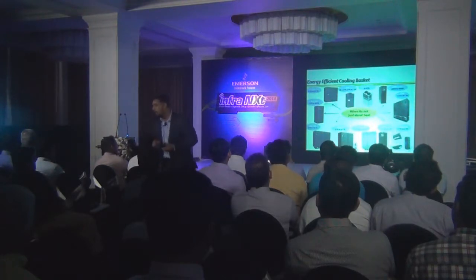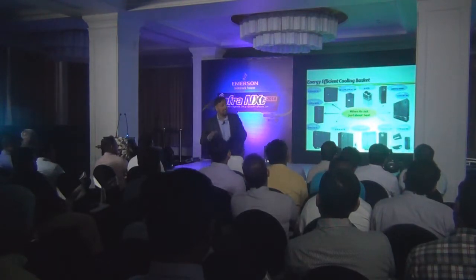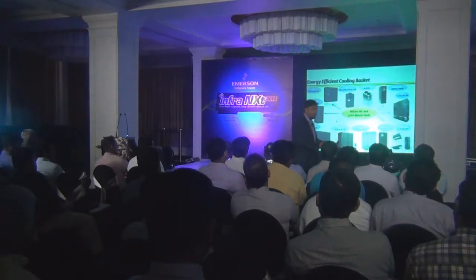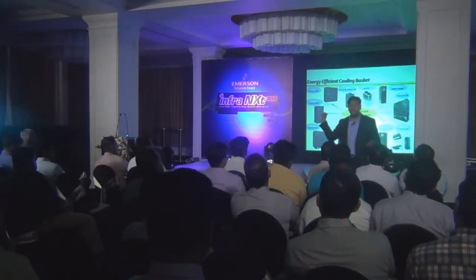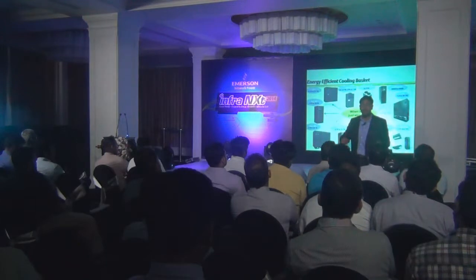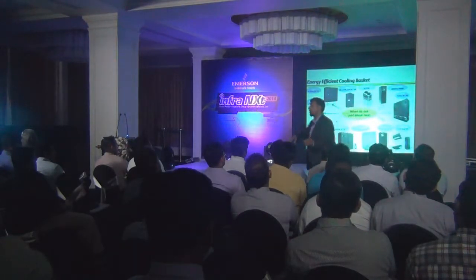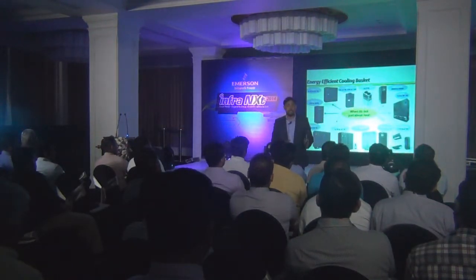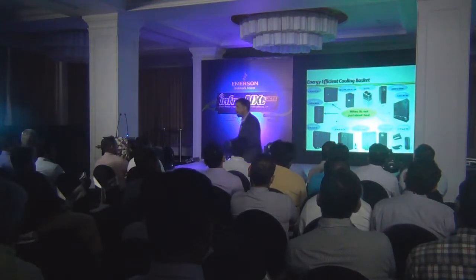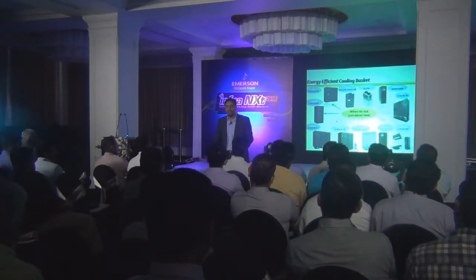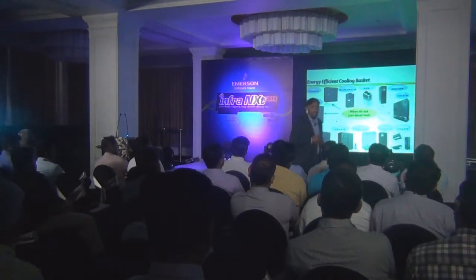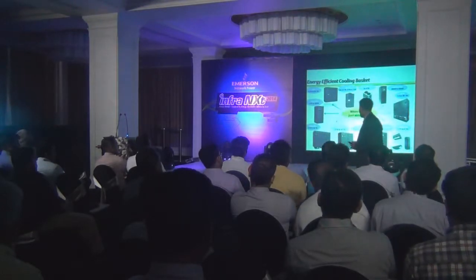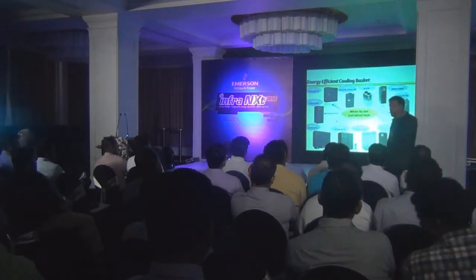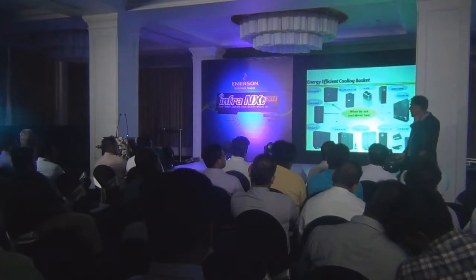But on the digital scroll, you get the best answer for this, because digital scroll is able to vary the capacity from 10% to 100%. The fan in the digital scroll unit is also variable type, and the condenser as well. So your entire system varies the capacity depending on the load requirement. It matches absolutely to the load requirement, and you deliver what you require and you pay for what you really use. So why should you be paying more than that? That's the point we are talking about here. So we have units up to 30 TR in such category in digital scroll.